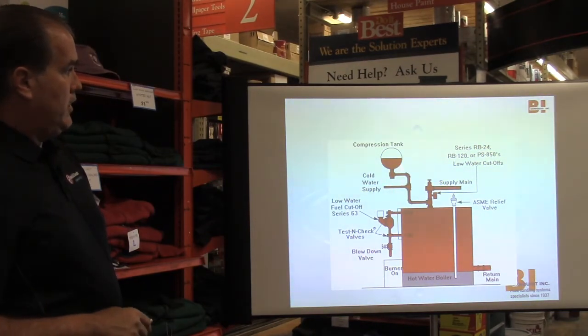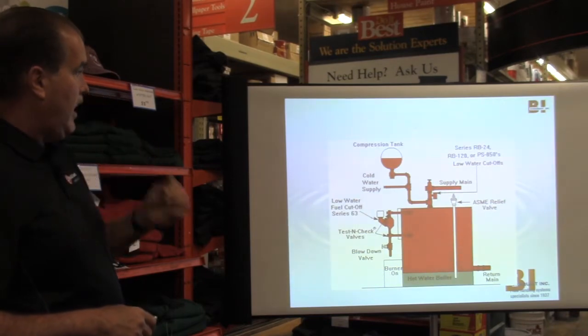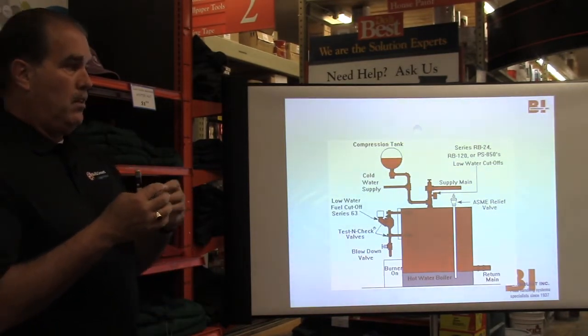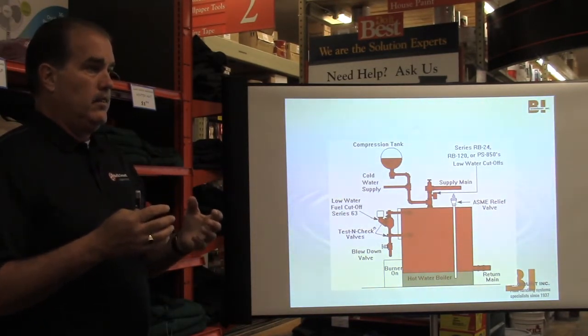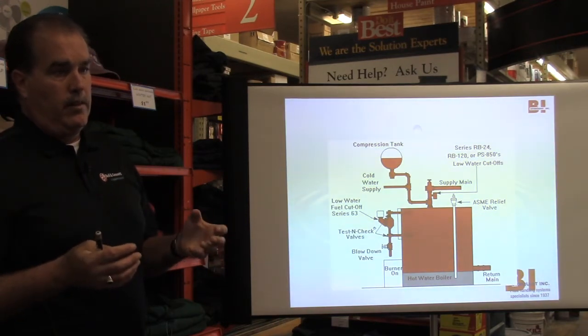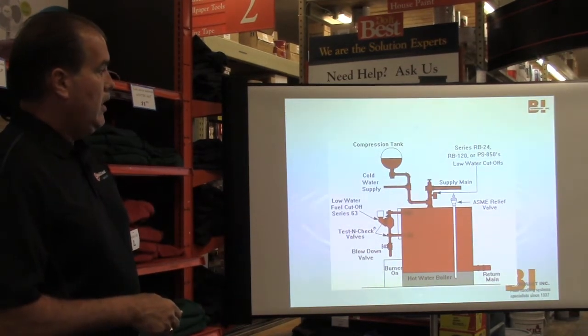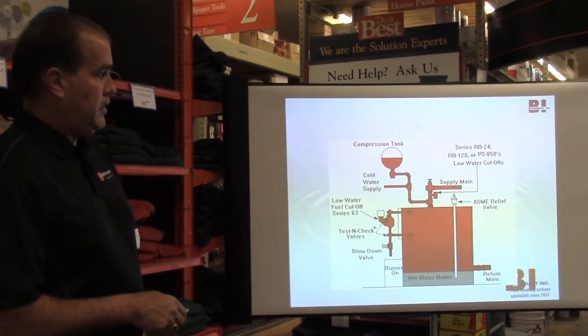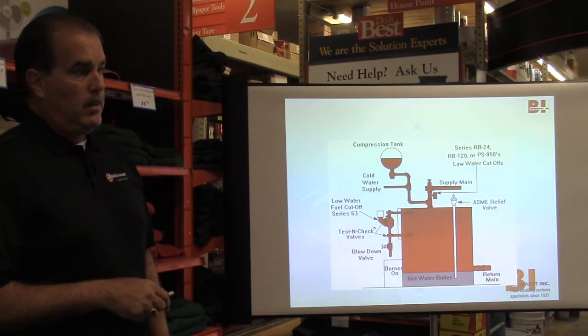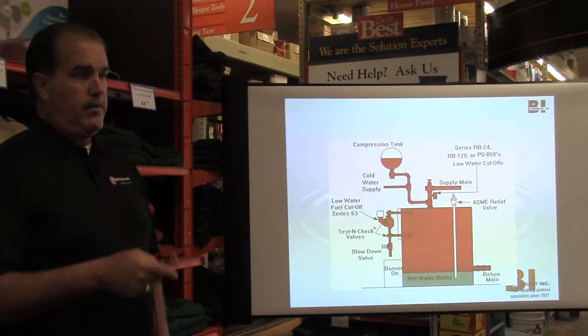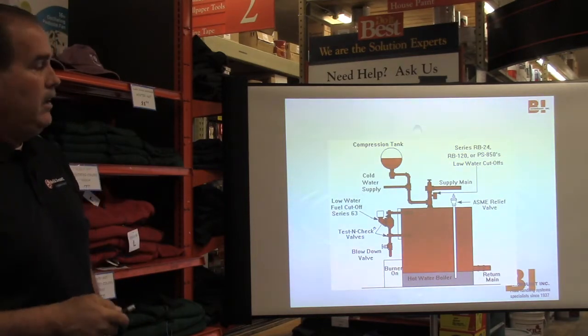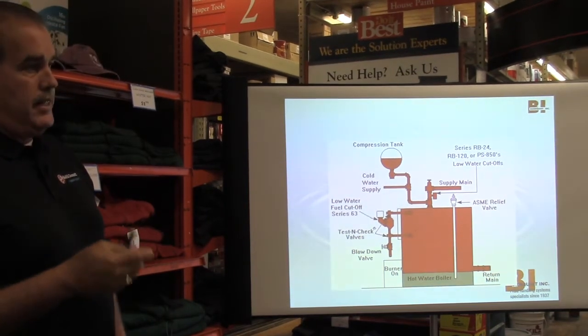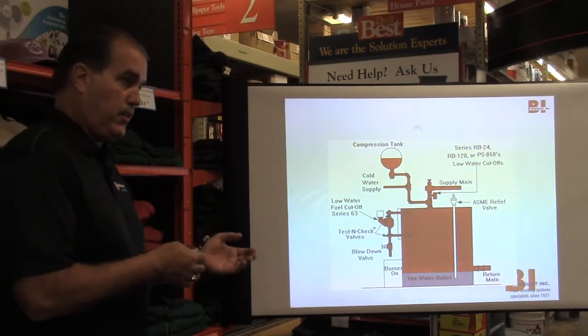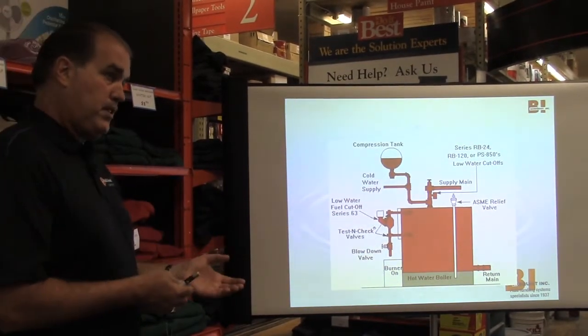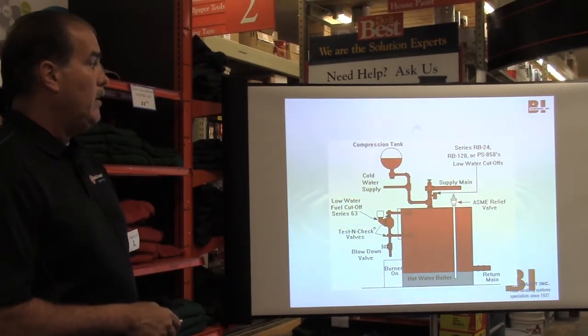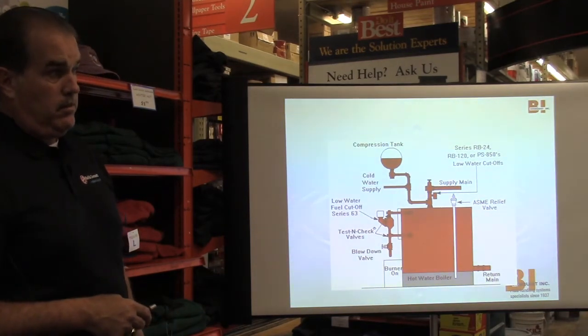This shows a compression tank. Okay, we'll start from the top. Water will expand as it's heated, so it has to have a place to go. If you didn't have this compression tank, you'd probably be popping what this guy is, which is a relief valve. Every boiler system has to have a relief valve. Sometimes it's called a T and P valve, which means temperature and pressure. Sometimes it's just pressure, but either way, for sure you need a pressure relief valve.